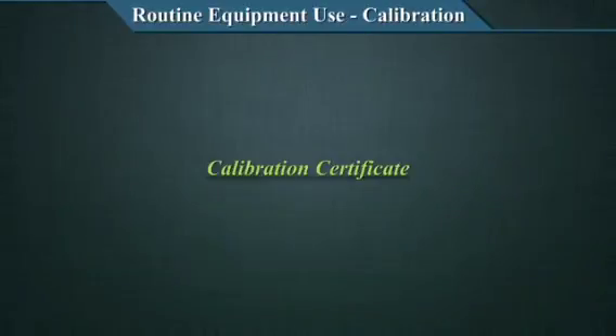So, the second resource that we have here is a calibration certificate. It's another very important piece of documentation in the event of calibration of equipment. After your calibration is done, the agency which is calibrating will issue a calibration certificate with traceability and all details required to understand and evidence your calibration, with the details of your uncertainty, your traceability, and other very valuable inputs in your certificate.